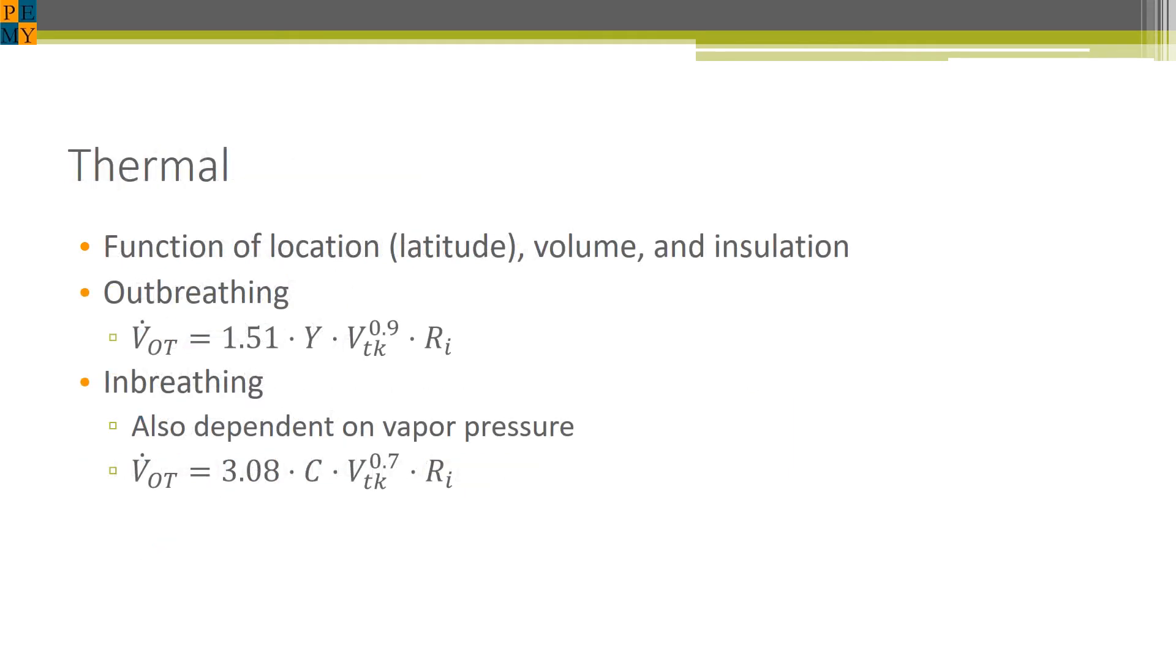For temperature or thermal effects on normal inbreathing and outbreathing, we see that the equations are dependent on the location because these determine the ambient conditions and temperatures of your tank. As an input, the API 2000 uses the latitude to determine where the tank is located. It's also dependent on the volume and insulation of your tank. For inbreathing, it's also dependent on vapor pressure because for volatile products, it can cause additional vapor generation. For these values, we look up in the table in API 2000 what these different parameters are to find these Y factors or C factors. The 1.51 and 3.08 are really unit conversions to help calculate these different values.